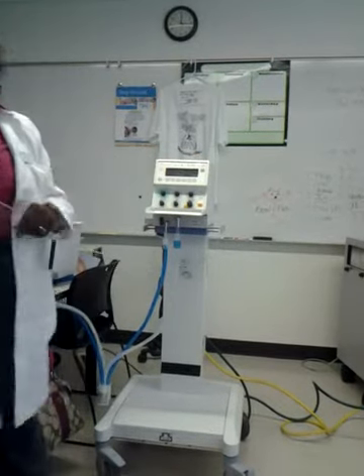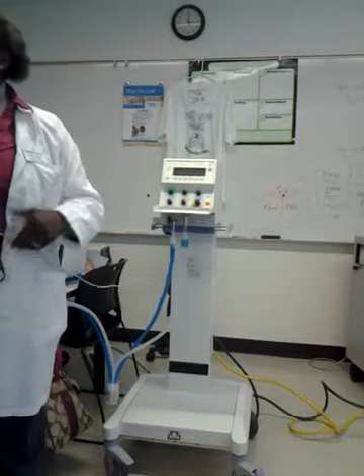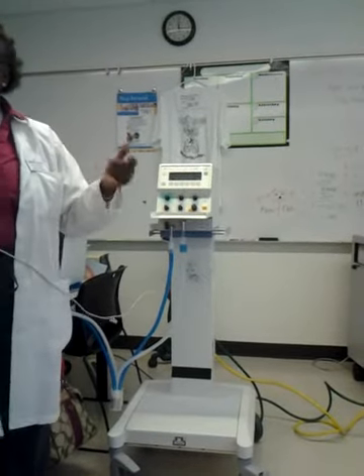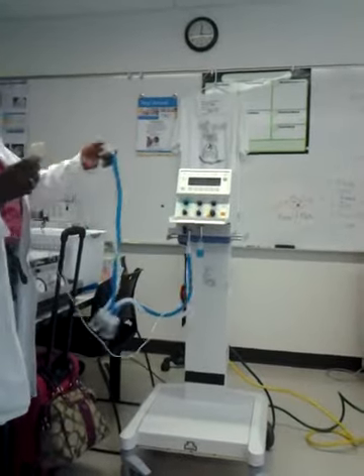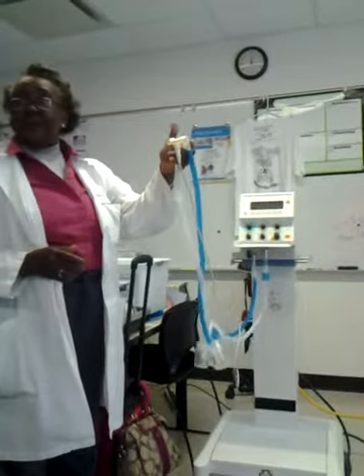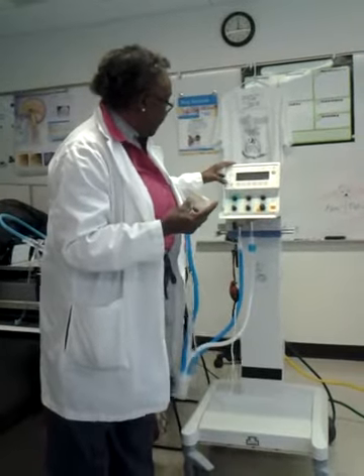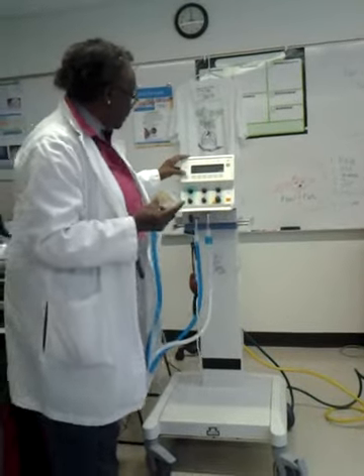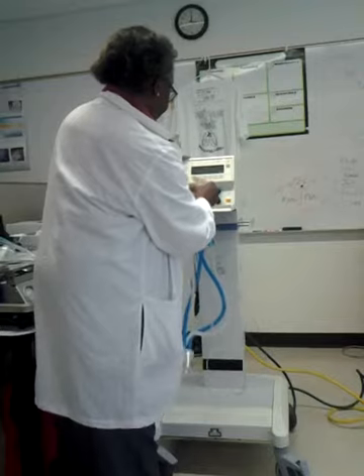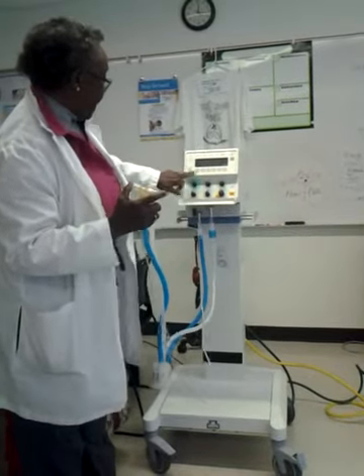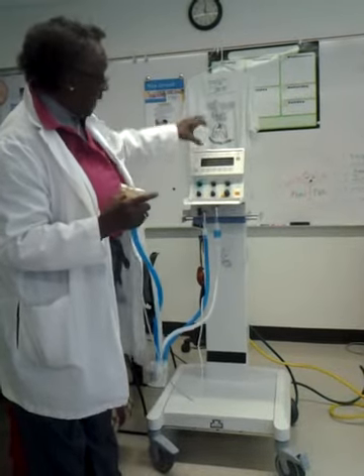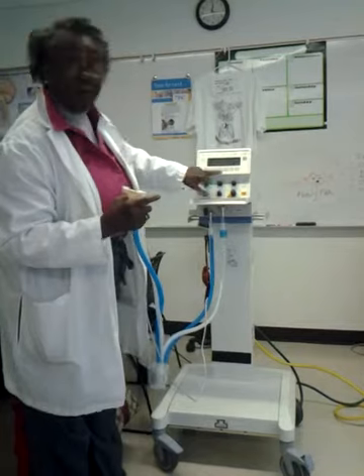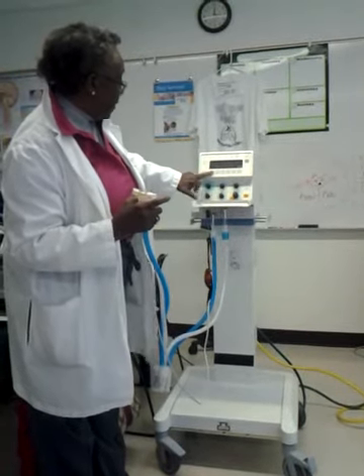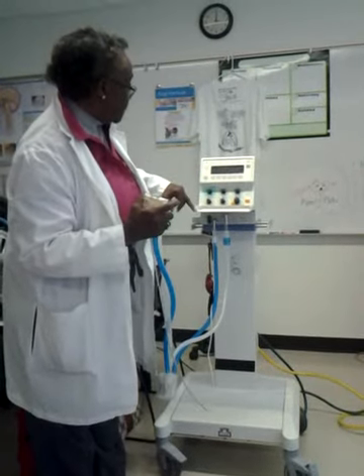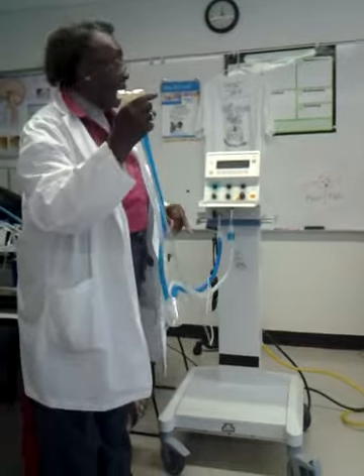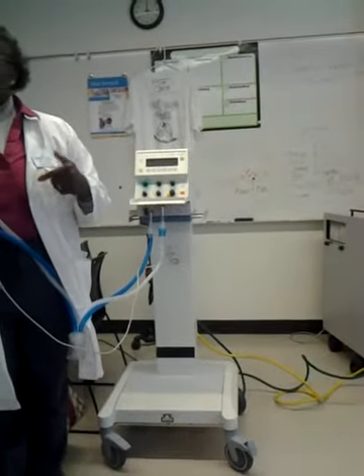A lot of the newer ventilators with the infants have a flow sensor that measures inspiratory flow as well as volume. And this is the inline between the patient and your Y. And when you put this in line, you're going to hit Cal configuration. Calibration configuration. And it says flow cal, O2 cal. It's going across the bottom here and it has a soft key underneath it. And if I hit the one under flow calibration, then it says start. And it's calibrating the flow. If you don't calibrate it, I promise you're going to get a lot of alarms and it's going to be going crazy on you.